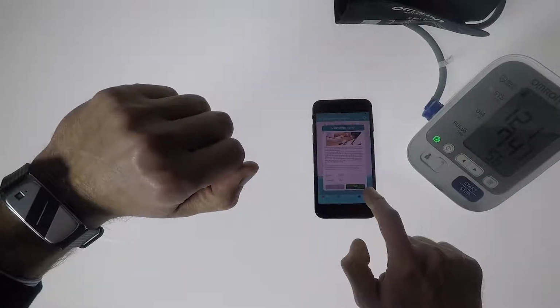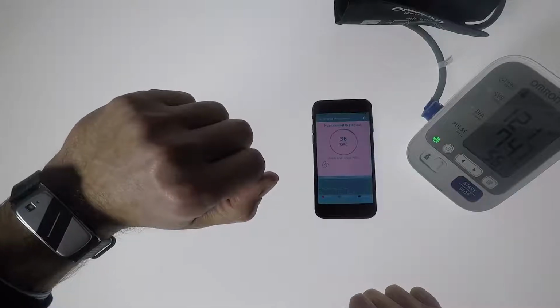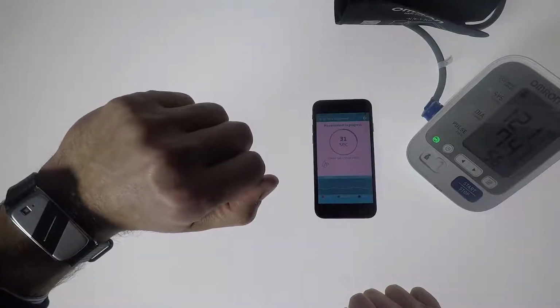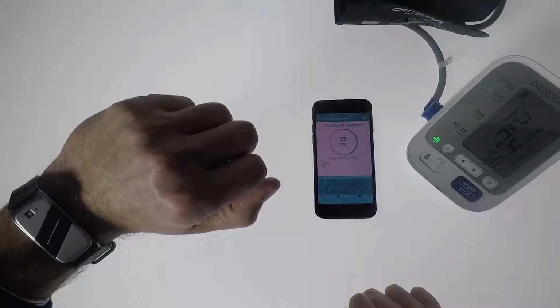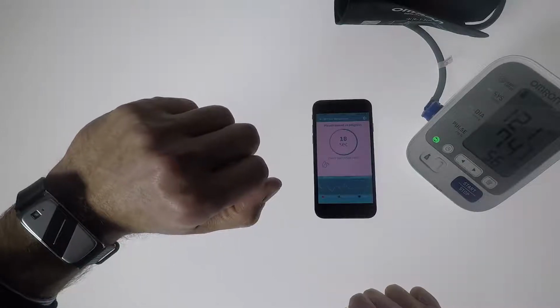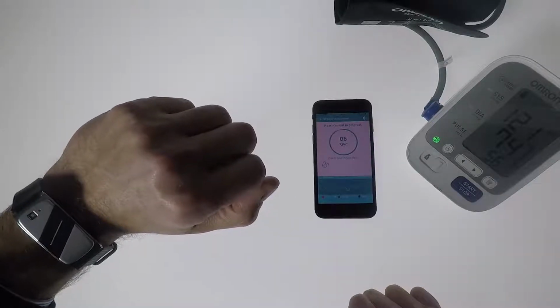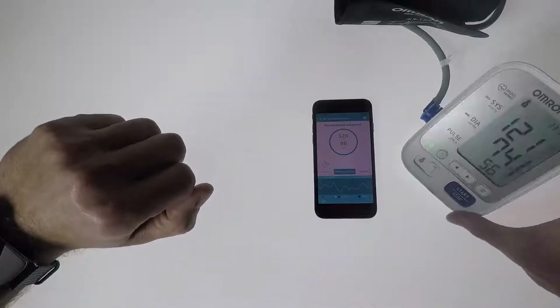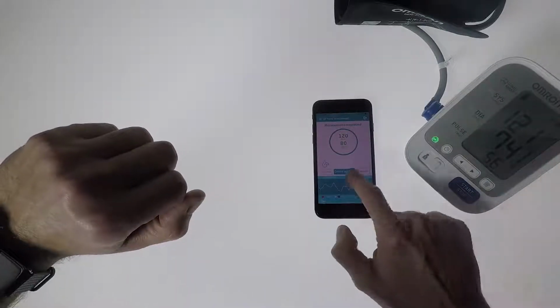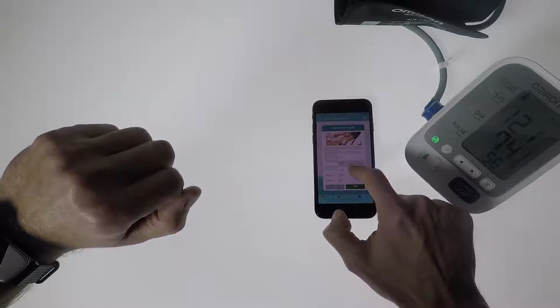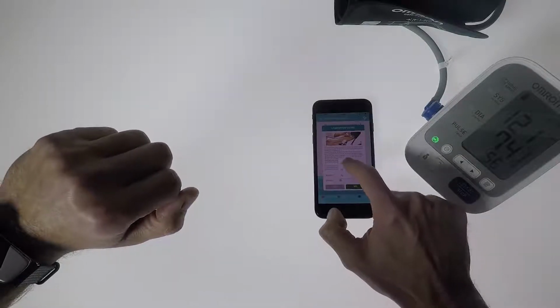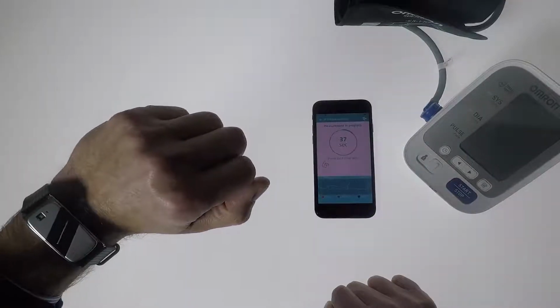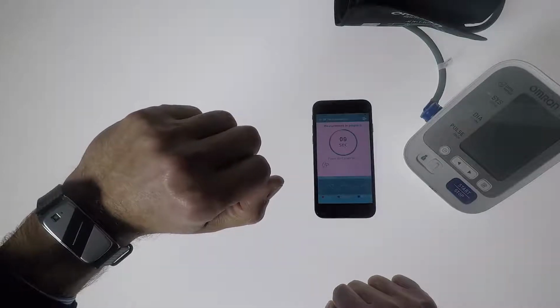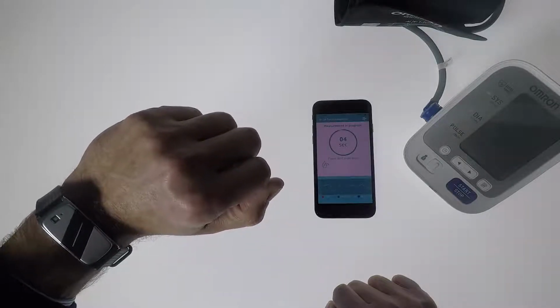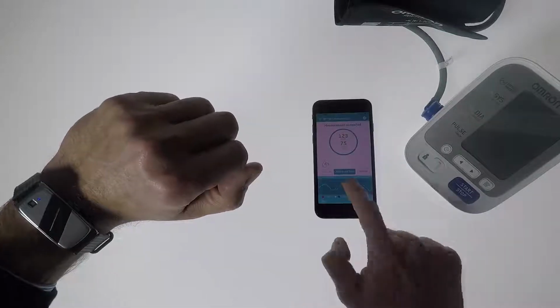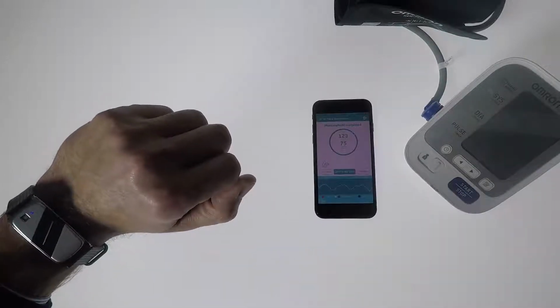This calibration is important to allow correct measurements of your blood pressure. You will also need to measure your pressure with a traditional blood pressure measurements instrument. If you don't have one of these, you can calibrate your Helo in a drugstore. At the same time, start a Helo blood pressure measurement from the left menu and wait for the countdown. When done, tap on Calibrate and insert the values collected with a traditional measurement instrument. When you finish this, the measuring will start again, and the instrument will be calibrated.